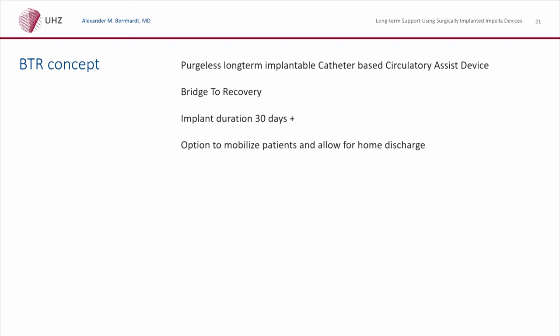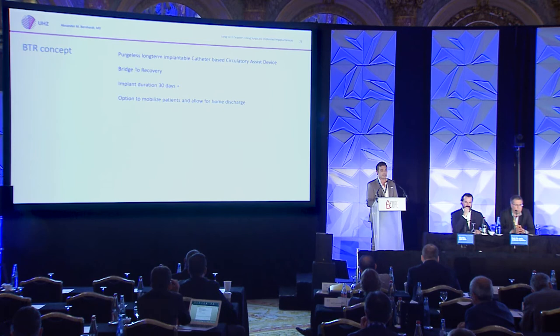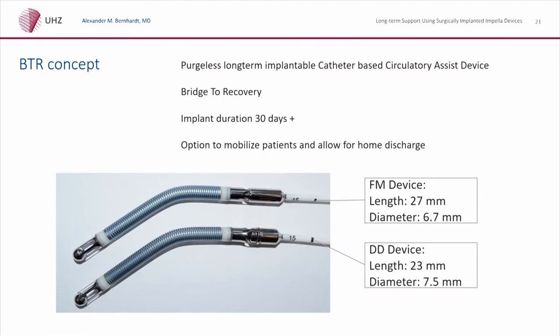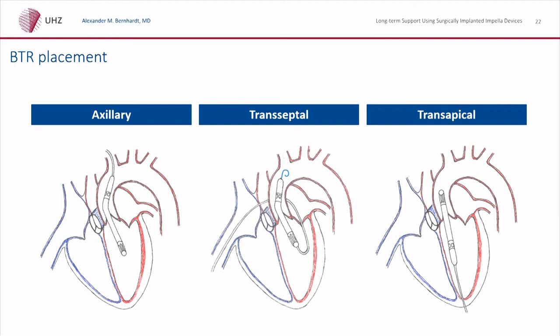What is in the future? There is hopefully a bridge-to-recovery pump — the goal is to have a pump that is purgeless and can be implanted for a long time, designed to recover patients. The approval is ideally longer than 30 days; patients could be on support for one year or longer and be fully mobilized and discharged home. There are many designs under investigation. Abiomed is thinking about its axillary approach, a transseptal approach, and a transapical approach — we will see what the future brings.